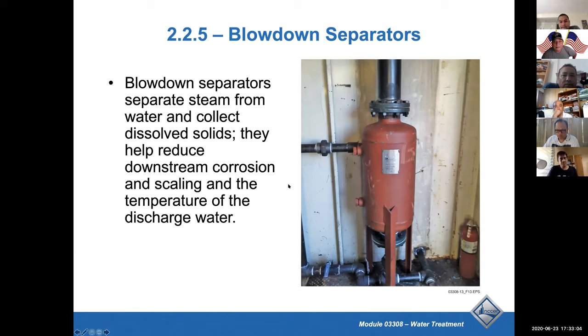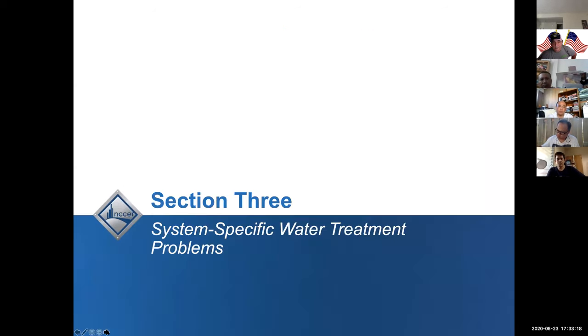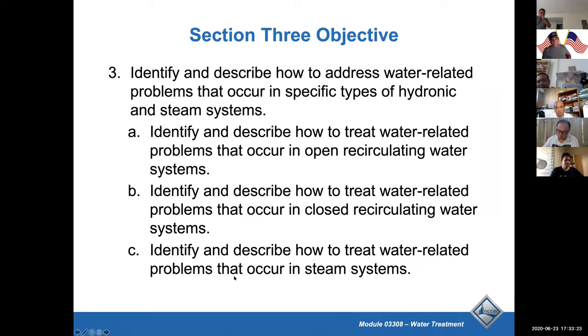Okay, blowdown separators. This is mostly for a steam system. They separate steam from water and collect dissolved solids. And it cools down the steam, the water being blown down. Okay. System specific.